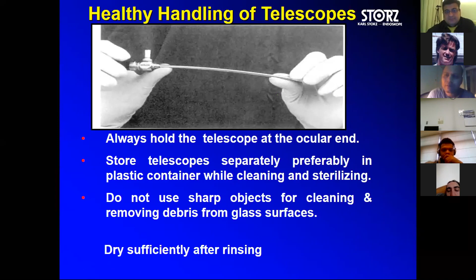Now, if you see the endoscope, when it is a therapeutic scope and there is a holder, many times unintentionally the surgeon can lock it on the shaft. Now, what are the disadvantages of locking on the shaft? First of all, we are giving you about 14.5 centimeter working length. That means if you are tightening on this shaft, you are losing this length, and sometimes you would like to go to the posterior part of the third ventricle and see structures like the suprapineal gland, suprapineal recess, lamina terminalis, and by locking on the circular shaft, it is not very comfortable.